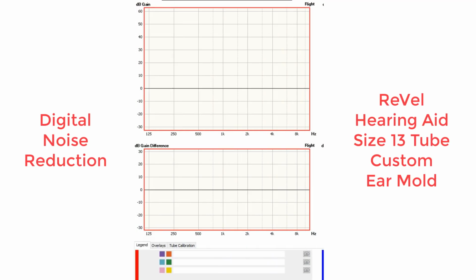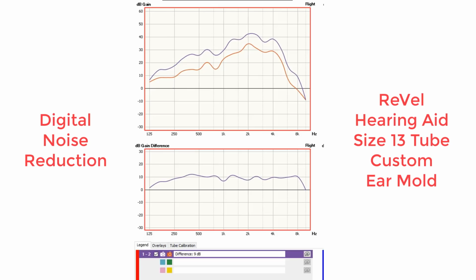So first I'm going to test the hearing aid that has a size 13 tube with custom ear mold, and what we want to see is that red line move further away from that solid purple line. Basically, I'm playing noise to the hearing aids and seeing how much of that noise it is reducing. And now when we look at the differences between the two lines, we see that there's about a 9 decibel reduction in background noise, which is very good.